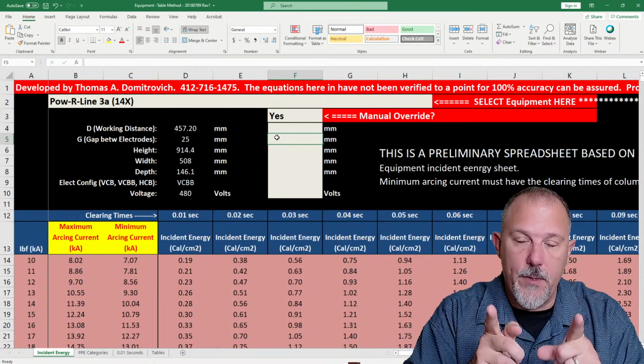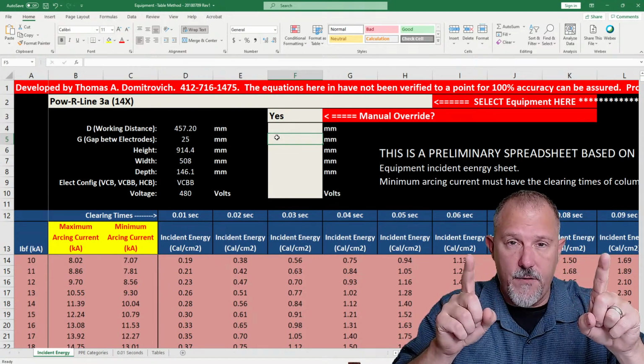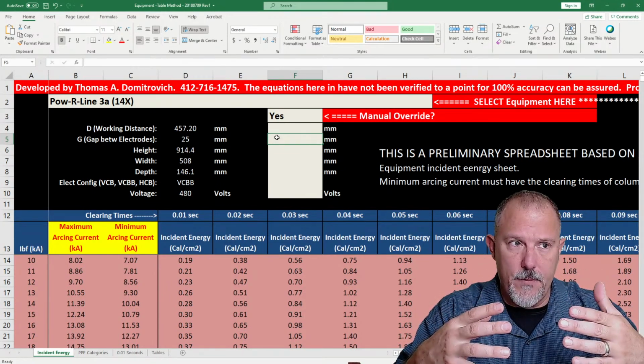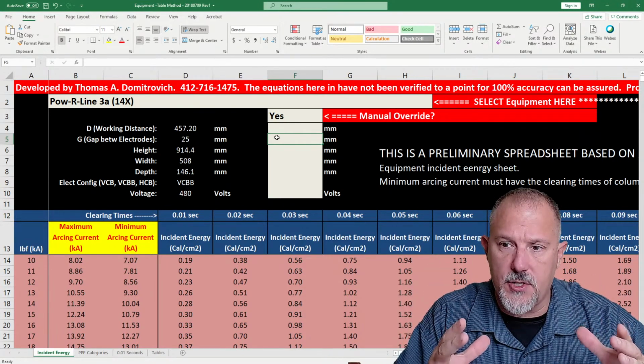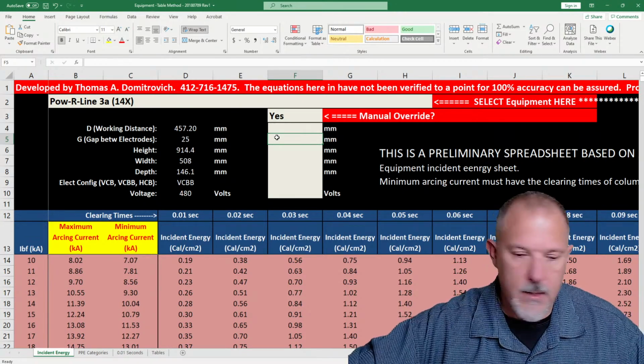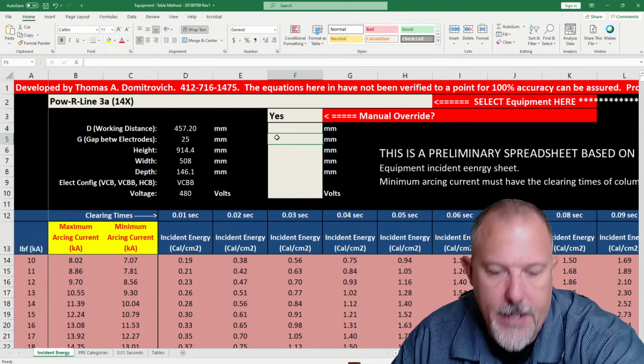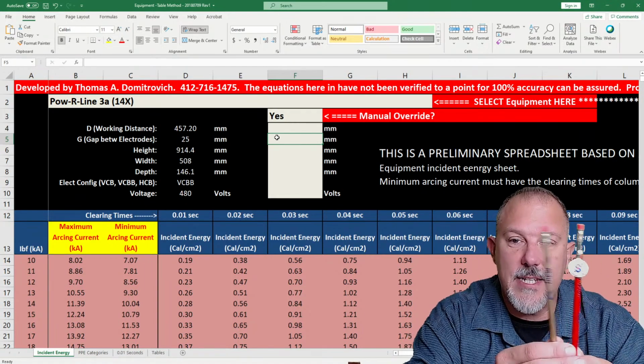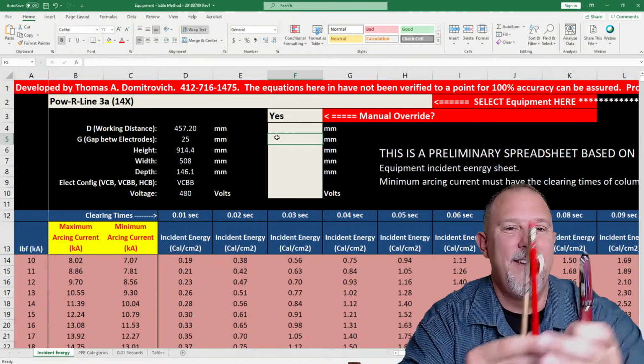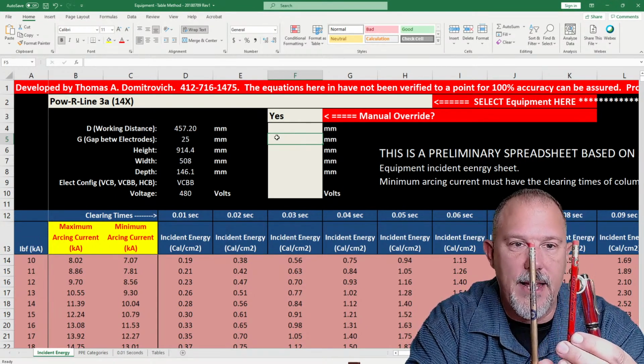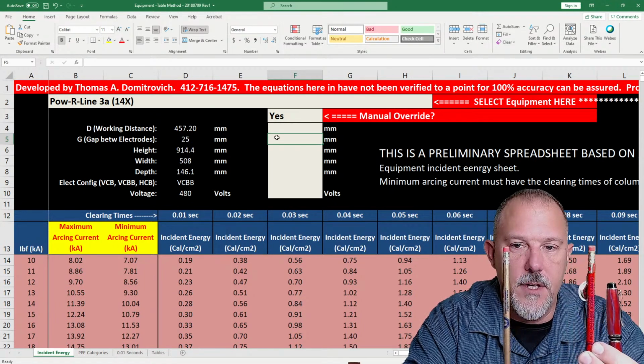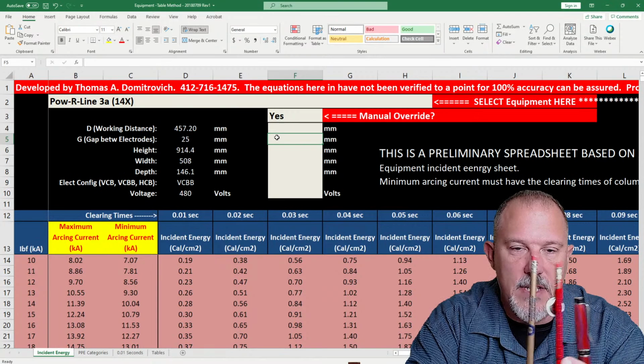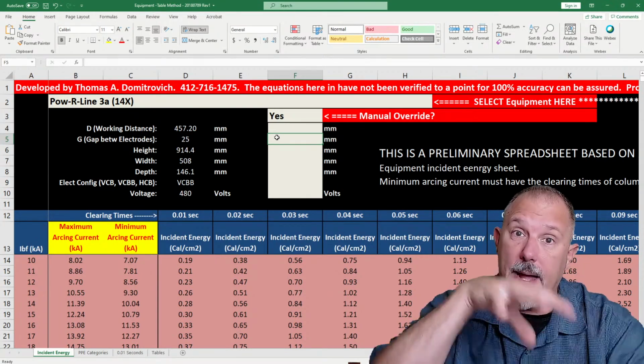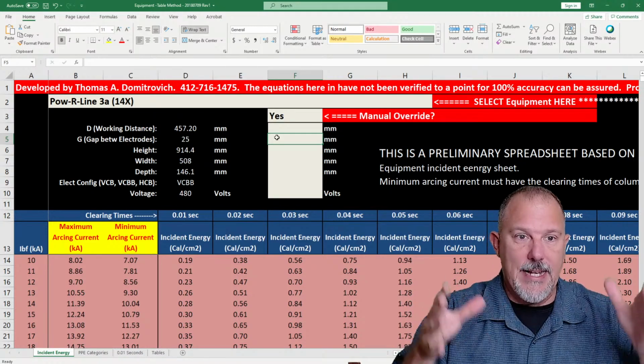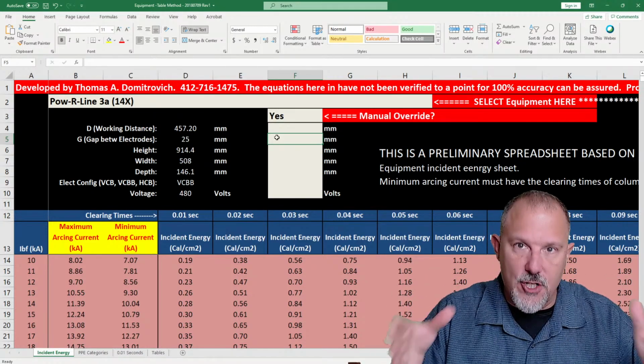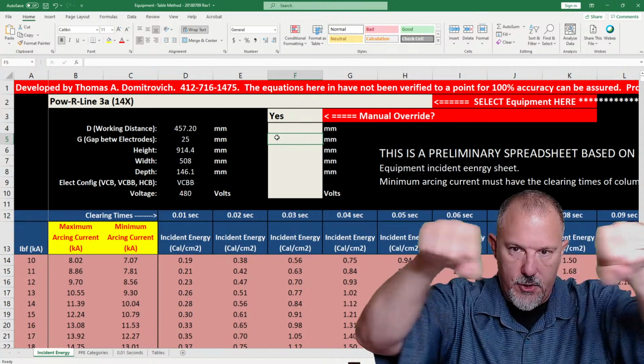So think about the gap between electrodes. What we did in the lab, we create what we call arcs in a box. You have 3 electrodes. I don't have anything that resembles a roll. Yeah, here we go. Let's say that these are electrodes. All right, I got 3 electrodes. And what I'm saying is this spacing could be 50, this could be 25, this could be 12. It's how far apart these are in my box. So that is my gap in between electrodes. I have bars, and I'm either this close or that far away.